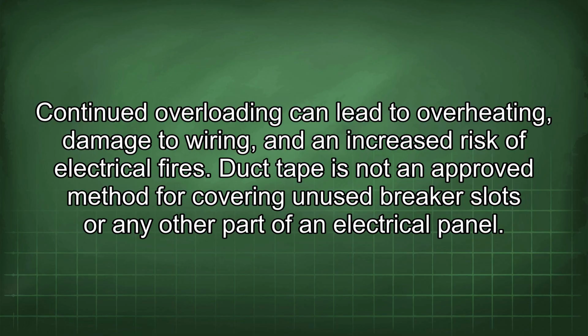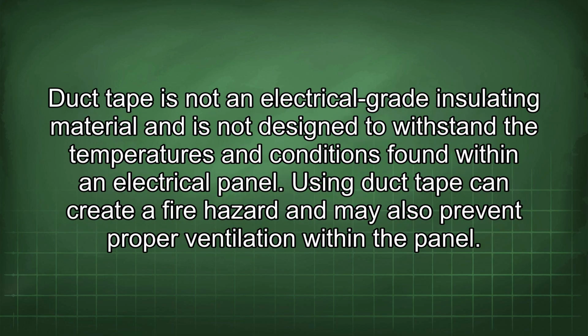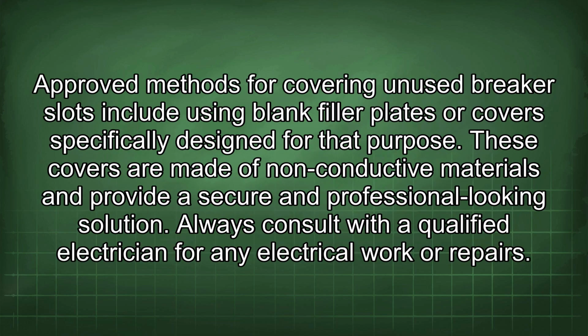Duct tape is not an approved method for covering unused breaker slots or any other part of an electrical panel. Duct tape is not an electrical-grade insulating material and is not designed to withstand the temperatures and conditions found within an electrical panel. Using duct tape can create a fire hazard and may also prevent proper ventilation within the panel. Approved methods for covering unused breaker slots include using blank filler plates or covers specifically designed for that purpose. These covers are made of non-conductive materials and provide a secure and professional-looking solution.